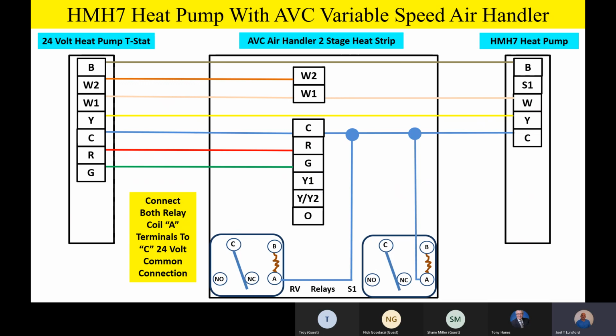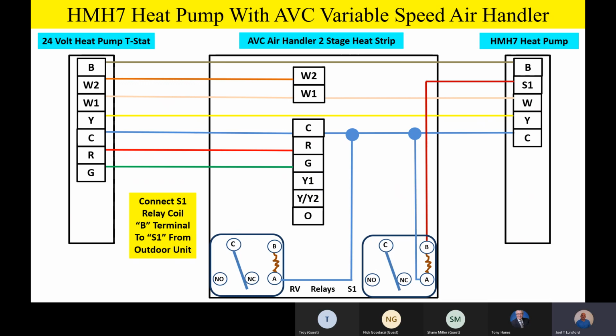Now, as we start hooking these relays up, we're going to take one side of both relays to 24-volt common. On the S1 relay, the relay on the right-hand side, the other side of the relay coil is going to hit S1, just like we had before, because we're going to energize that S1 relay for airflow reduction.